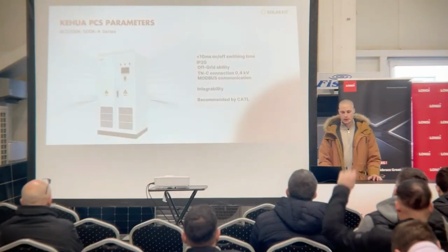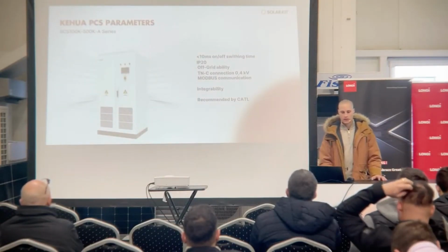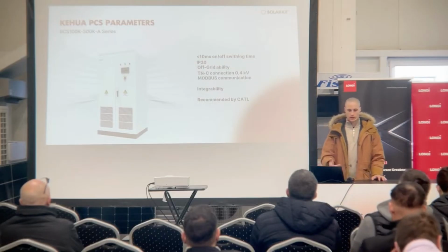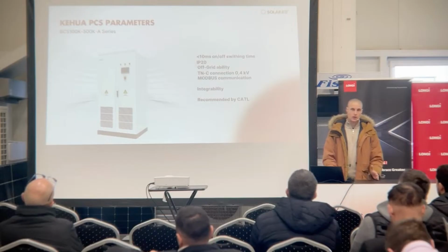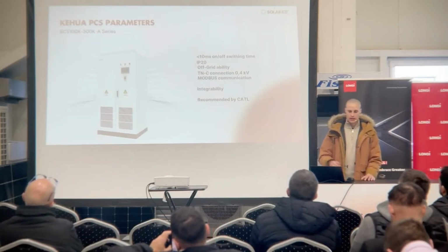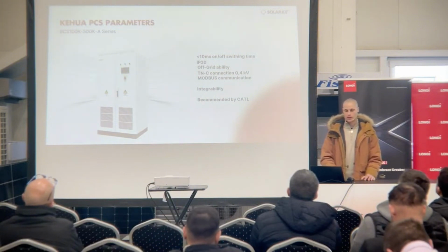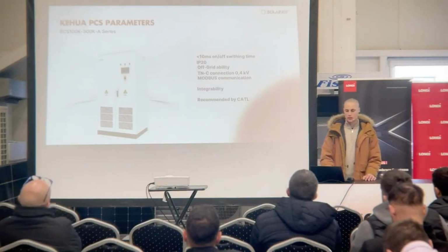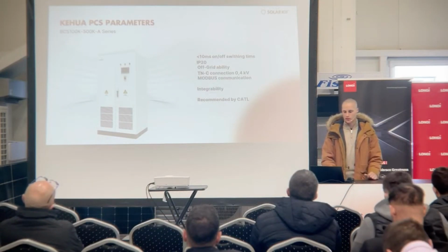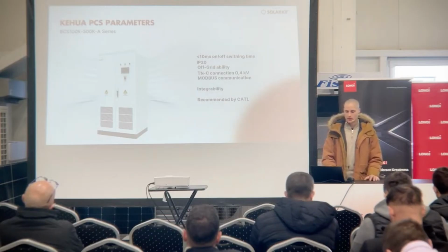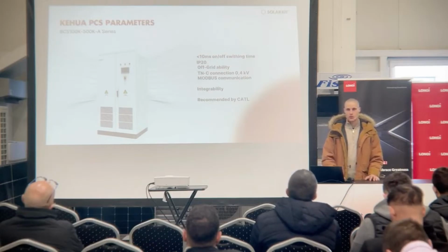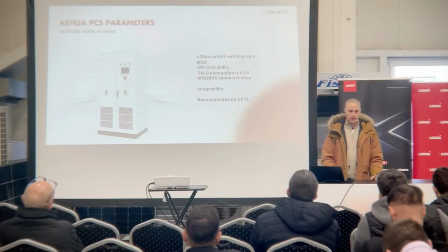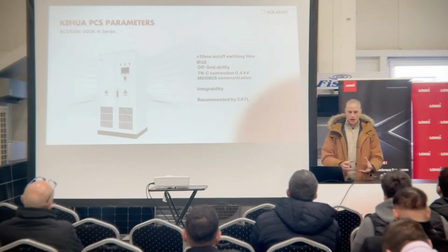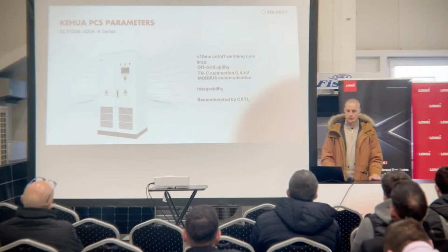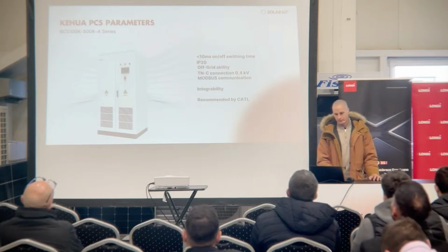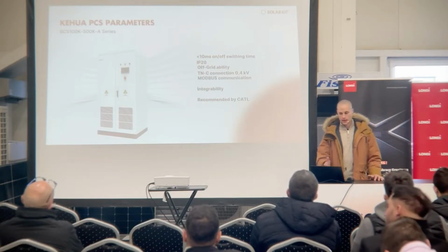From their PCSs, I would like to mention two different types. One is the transformer version - this is an on-off grid switching cabinet, ranging from 100 kilowatt to 500 kilowatt. It has the transformer inside, it has switching cabinets inside, because it can also switch to off-grid mode within 10 milliseconds, so you have the UPS function. One thing to mention is that it's only IP20 rated, so you have to build some kind of switching house around it to prevent water and the environment from reaching inside. So it's not meant for outdoor use, but it has the off-grid ability also.